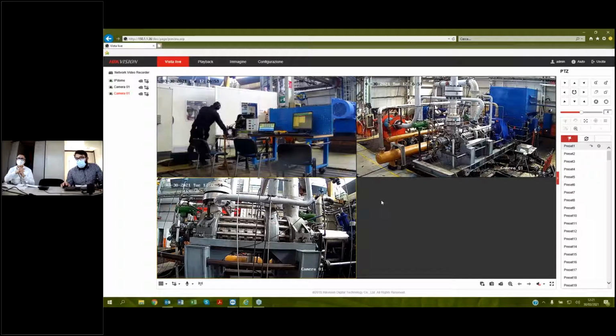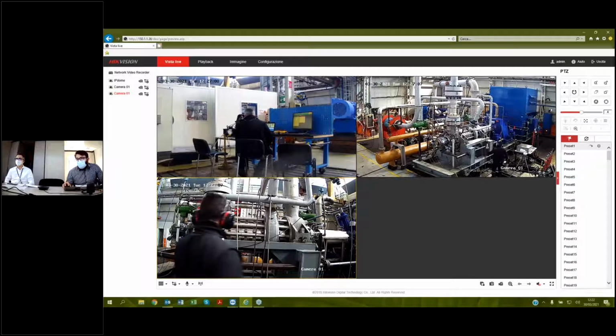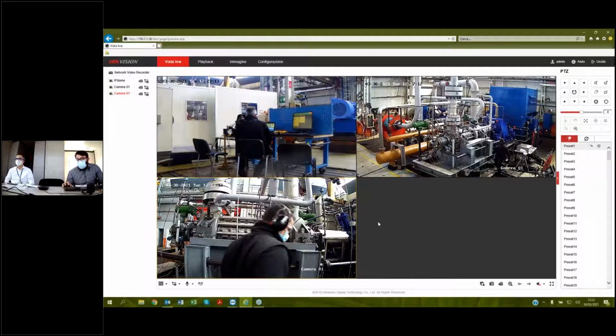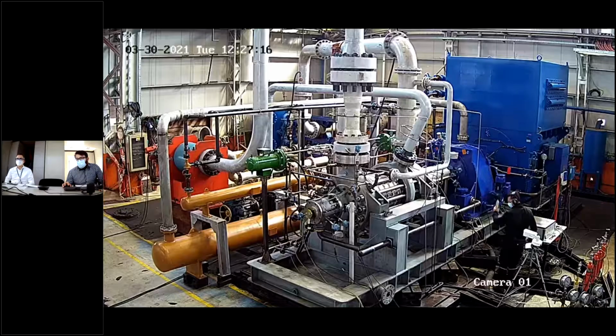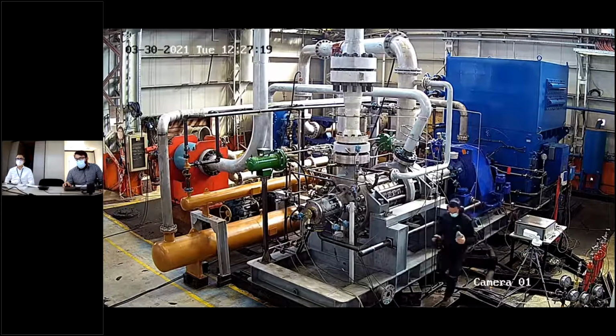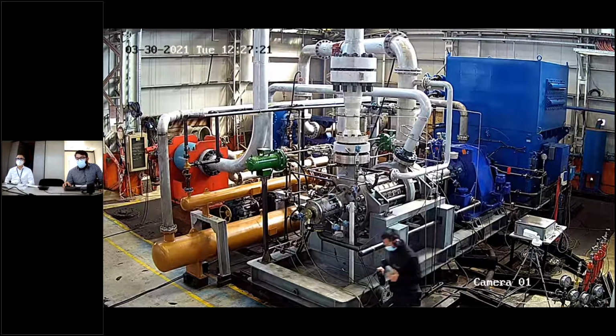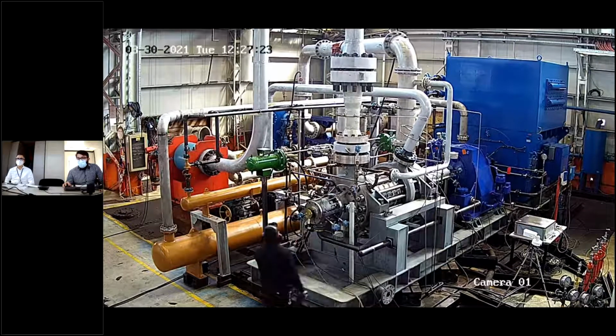Using a portable vibrometer and a phonometer, the operator can check the levels. The measurement of vibration gives us an RMS value. It is a root mean square value. It is in velocity, so millimeters per second. The measurement of sound provides that we have 8 points of measurement at 1 meter far from the skid.